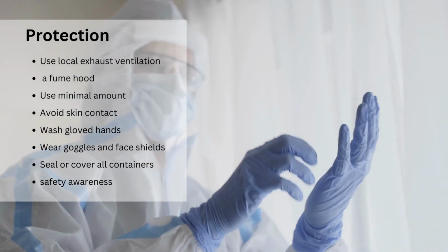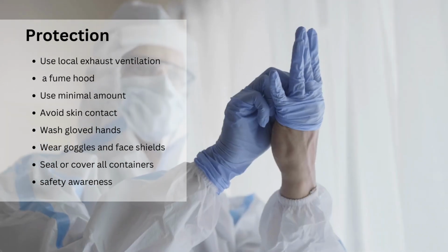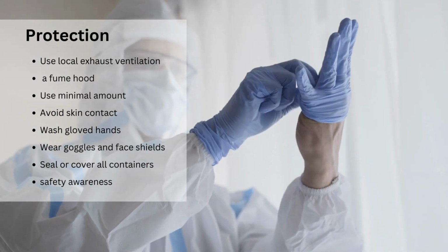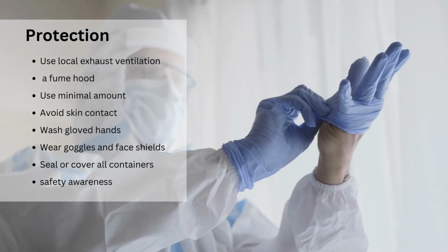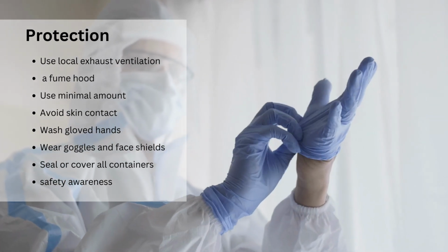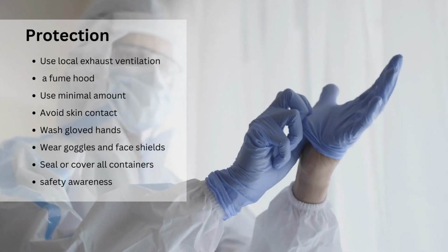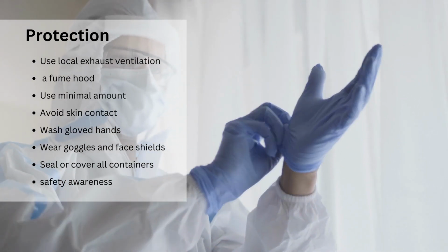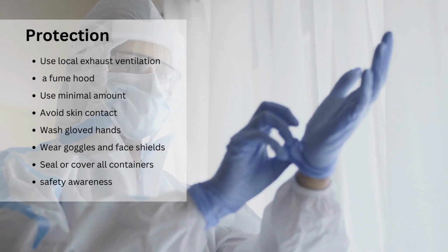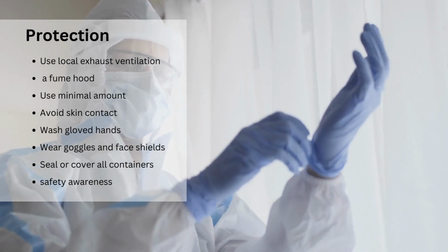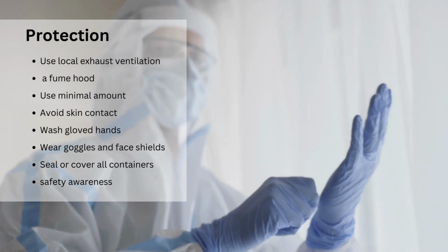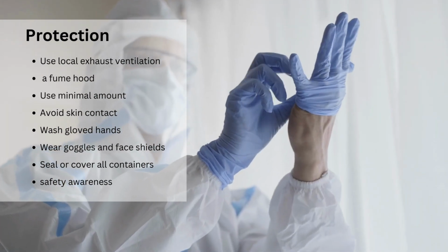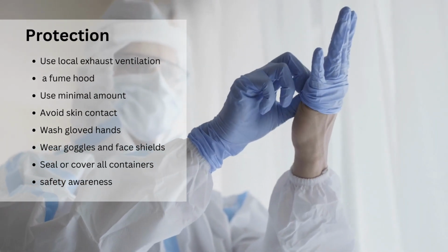We must wear goggles and a face shield while handling glutaraldehyde so that the eyes are protected. All glutaraldehyde solutions must be sealed and covered properly after use. The container must be tightly capped after it is used. And the people who are involved in the use of glutaraldehyde must be properly trained in these safety measures.